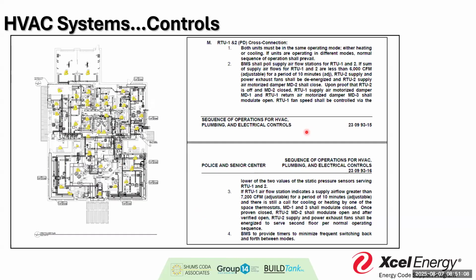Some of these different control sequences say when this forced air system is on, this boiler-based radiant heating system is going to be off. We don't want to cool with one and heat with the other and create a sauna unless it's intentional.